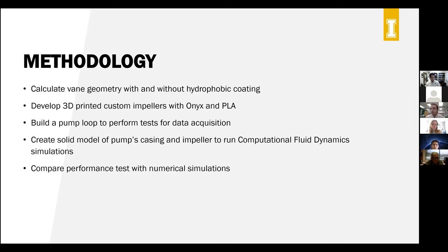And then to do those things, the key important methods we had to figure out and determine was what vane geometry to choose. So we had to calculate vane geometry with and without hydrophobic coating, so changes in friction and how that affects efficient vane geometries. We had to develop 3D printed models and impellers with 2 different materials to test those outcomes, build a pump loop to test those in real time and acquire data for efficiency data manipulation, and create a solid model of a pump casing and impeller to run computational fluid dynamics simulations. This is important in terms of validating our findings and providing further understanding of what is actually happening in the pump casing, and then compare those performance tests with numerical simulations.